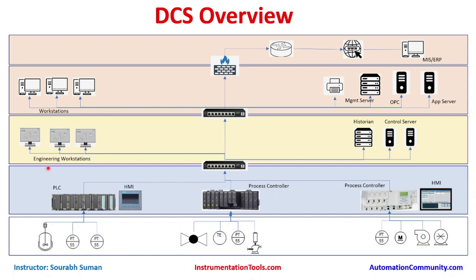The purpose of the engineering workstation is to configure the system. We also have historians, whose purpose is to save analog process data, digital process data, or whatever we configure. A historian is a large server with good storage capacity, or it can be software that saves data to a NAS or SAN drive on the network, depending on the type of DCS.